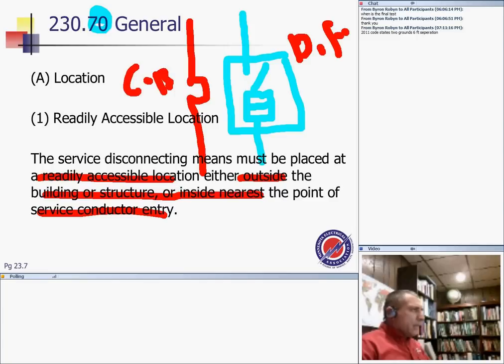A few things about service disconnect, and I know we jump a lot. A couple of things that come to my mind for service disconnect: for residential, since we talk residential, the minimum is 100 amp. You can't have a smaller than 100 amp service for residential. 60 amps for non-residential minimum, with some exceptions. 60 for non-dwelling, with some exceptions.